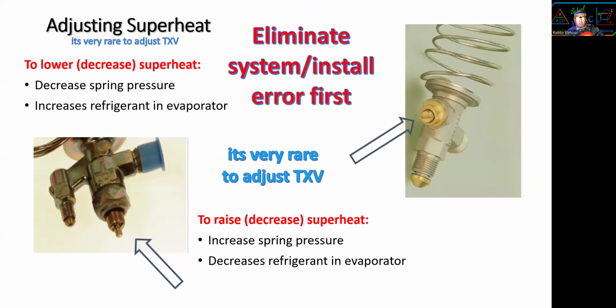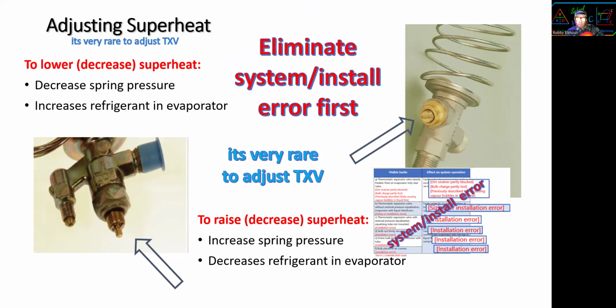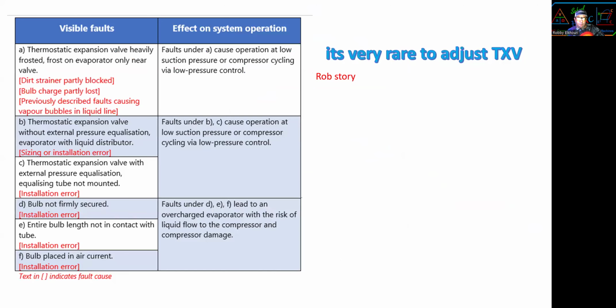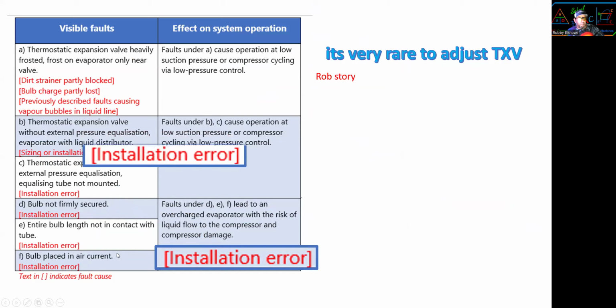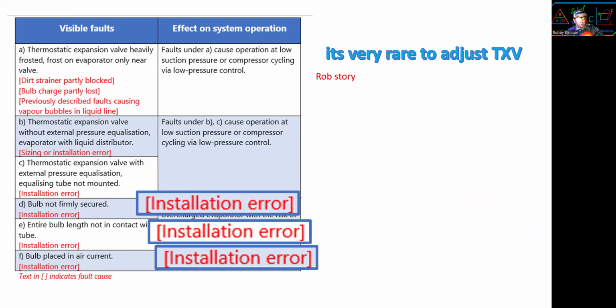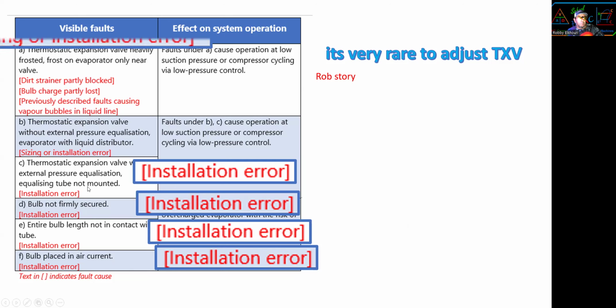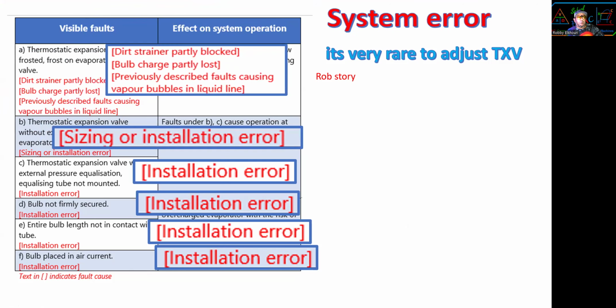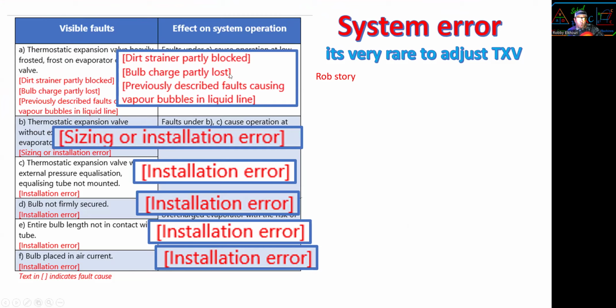It's very rare to adjust. Eliminate system and install errors first. System and install errors, we're going to cover that next. Ready? It is very rare to adjust a TXV. Installation errors: the bulb is not in contact with the tube. The bulb is placed in the air current and is not insulated. The bulb is not firmly secured. The thermostatic expansion valve's external pressure equalizer is not mounted. All of these are sizing and install errors. This is high side, dirty strainer, low side problems, restriction errors, system errors.